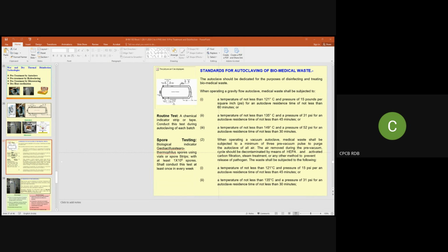One is called the routine test, and this test has to be conducted for every batch. Whereas the spore test has to be conducted when you are treating the waste using the autoclave, and vials of spores are used, like a biological indicator, like Geobacillus stearothermophilus. Spores have to be used for the purpose of ensuring the efficacy of the autoclave.